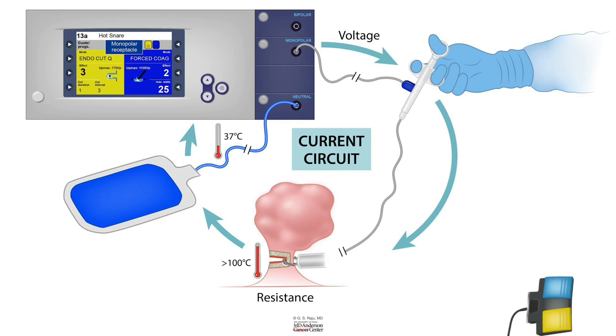So now that you have the circuit complete, as you can see here, we've learned about the electrical circuit, starting with the generator, creating the voltage. From there, the monopolar electrode takes the current to the snare, which is a monopolar device, and from there to the tissue, the stalk of the polyp, and from there to the dispersive pad or the returning electrode. It is not a grounding pad, it should be called dispersive pad, and then back to the neutral socket of the electrosurgical generator. As you can see here, the main purpose of the dispersive pad is to distribute the returning current over a wider area so that the temperature doesn't increase there.